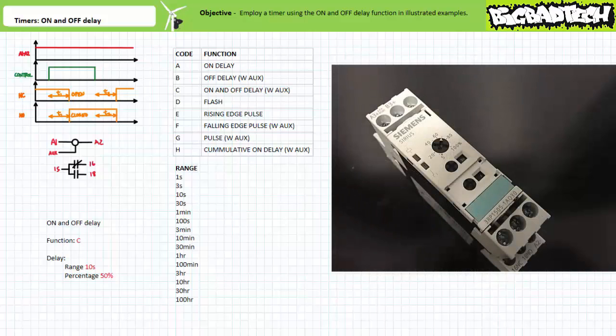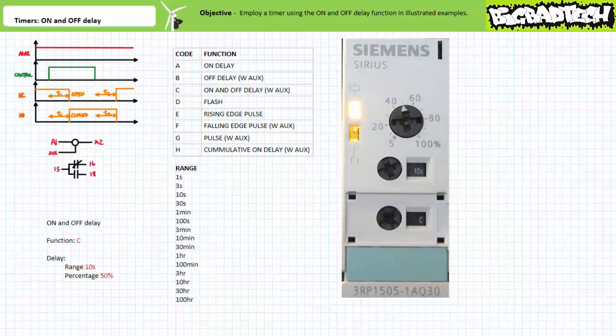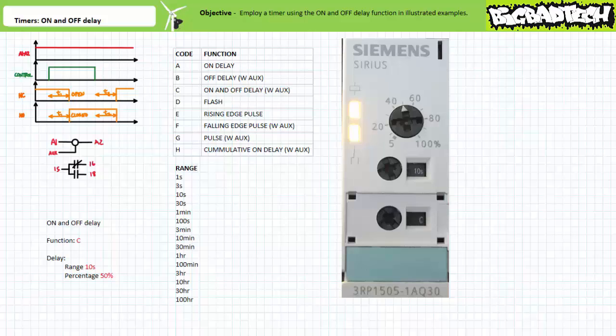This particular manufacturer necessitates a two-step process to adjust the delay period: first select the range, then adjust the range percentage. The range selection presents possibilities from one second up to 100 hours, and the percentage fine-tunes the delay within that range — for example, 50% of 10 seconds would be a delay of five seconds. Note this timer has two indicator LEDs: one indicating when the device is powered up and another indicating when the outputs are in their activated state. You know you set up the on and off delay timer correctly if you assert the auxiliary input, wait five seconds, see the output change states, then de-energize the input, wait five seconds, and see the outputs return to their deactivated states.